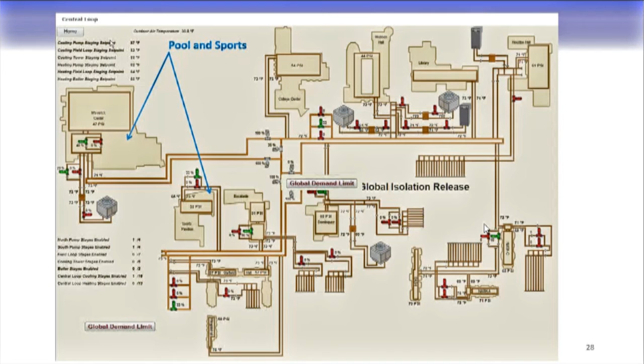Some of these things have their own bore fields and can be shut off, just like a water system — I can regulate it. Over the last 11 years we've had one leak, which turned out to be an electric fusion coupler that wasn't properly installed. But we were able to isolate the loop into about 7 different sections and find where that leak was. Every building has shut-off valves, so we have a global demand, and they all share the same fluid. There's no antifreeze, except where we have something on the roof — there we have a heat exchanger with the main system and an antifreeze glycol loop that goes to the roof.